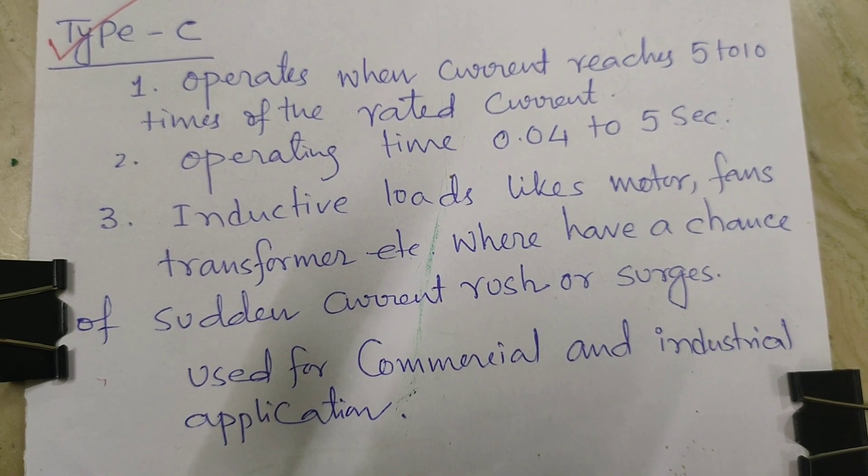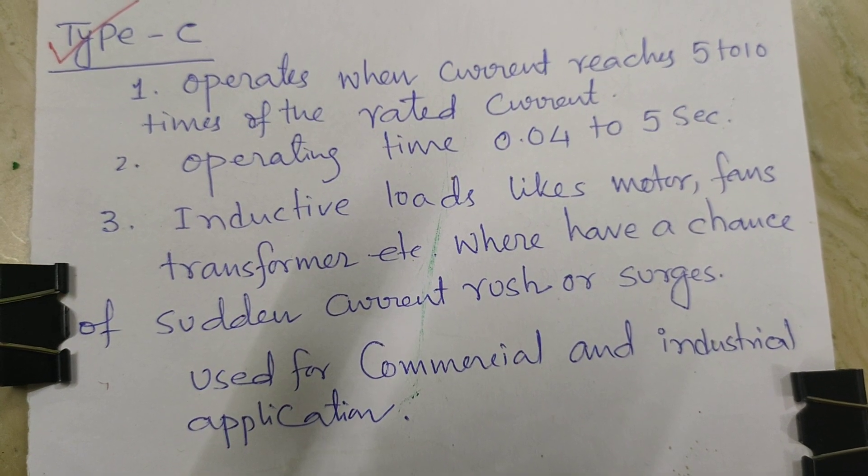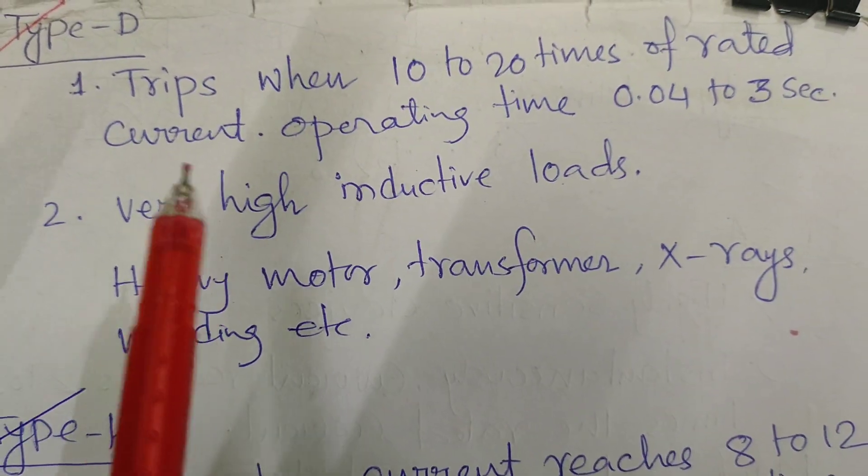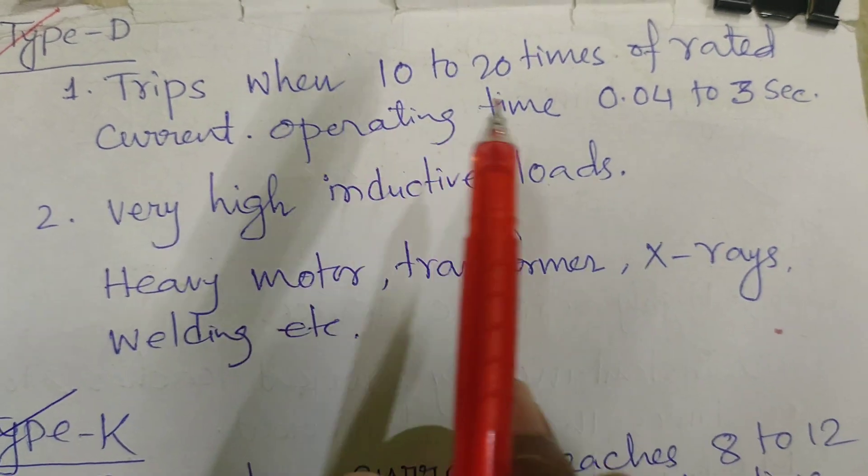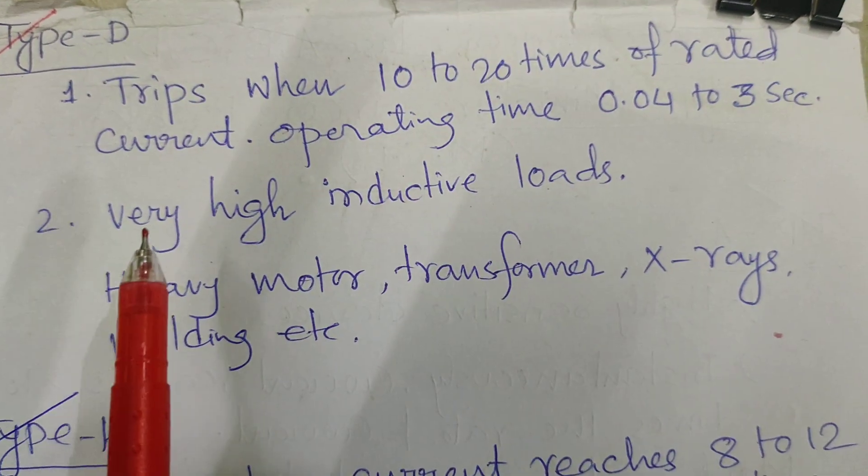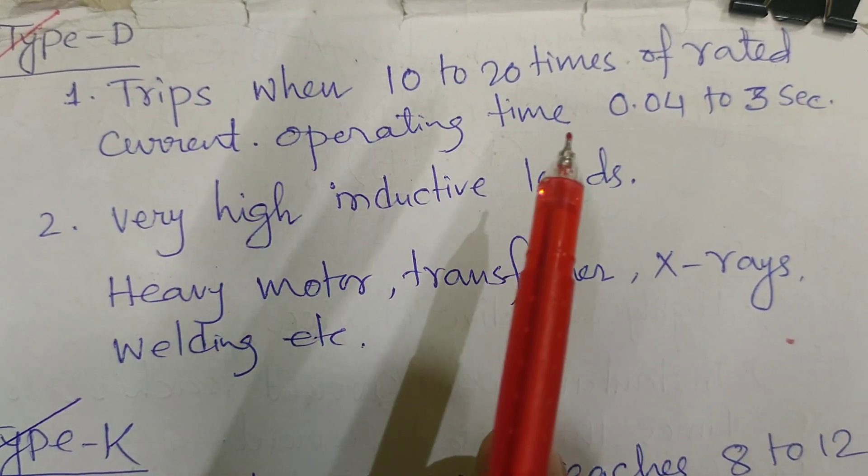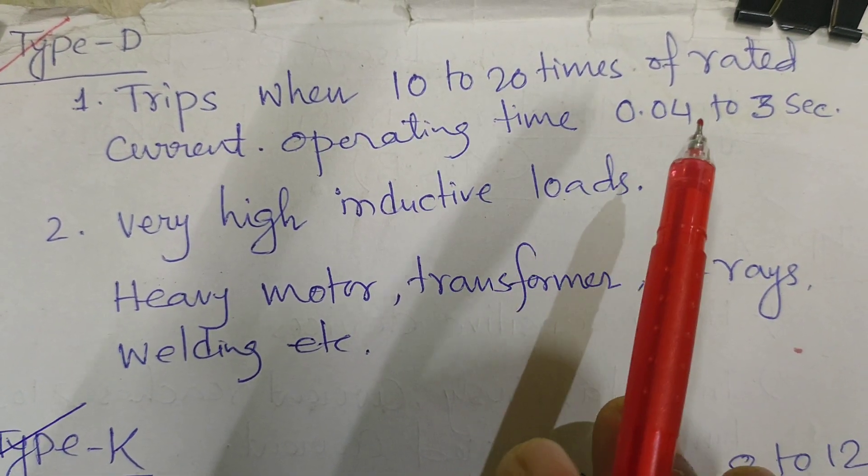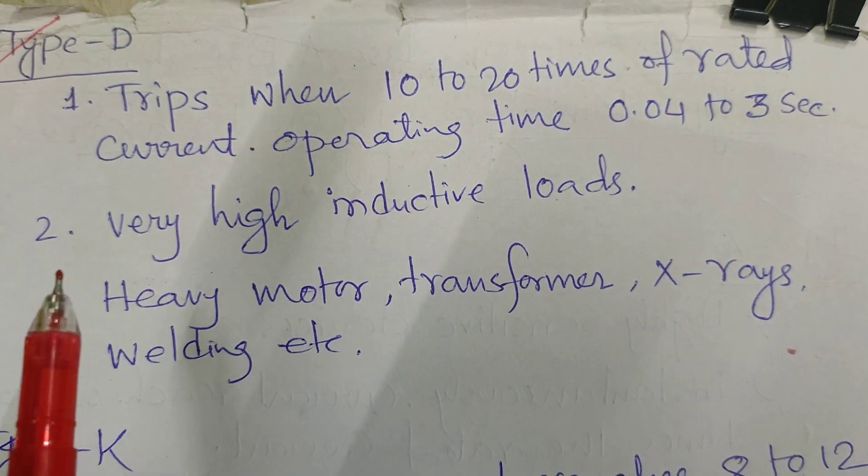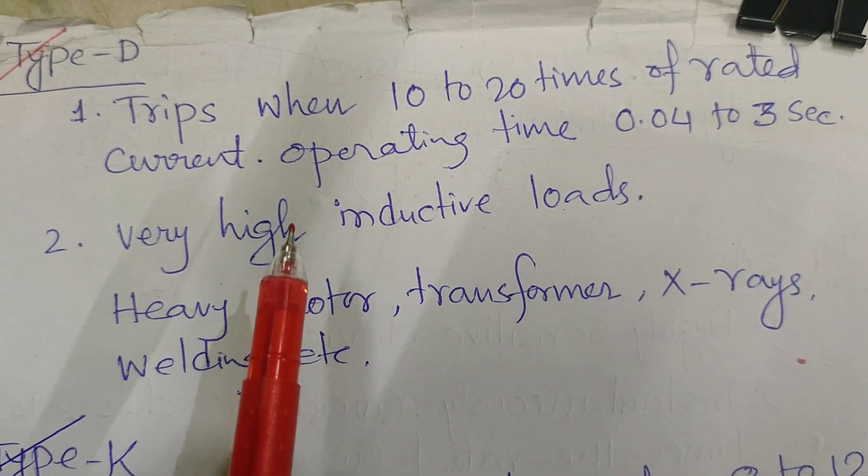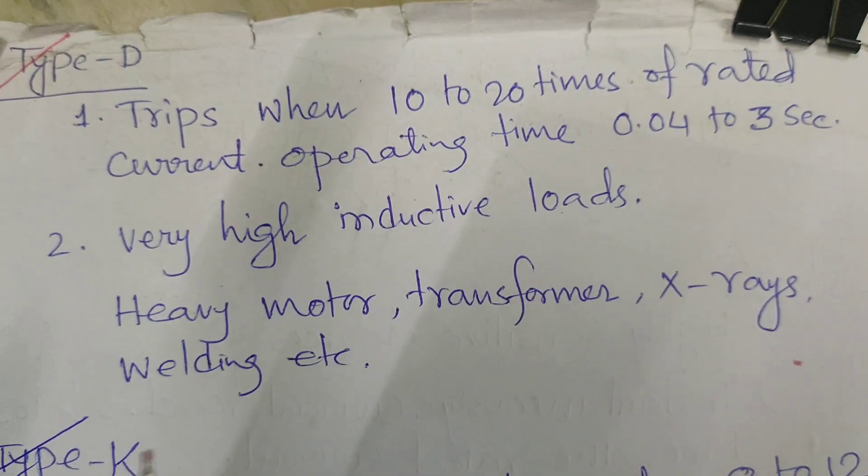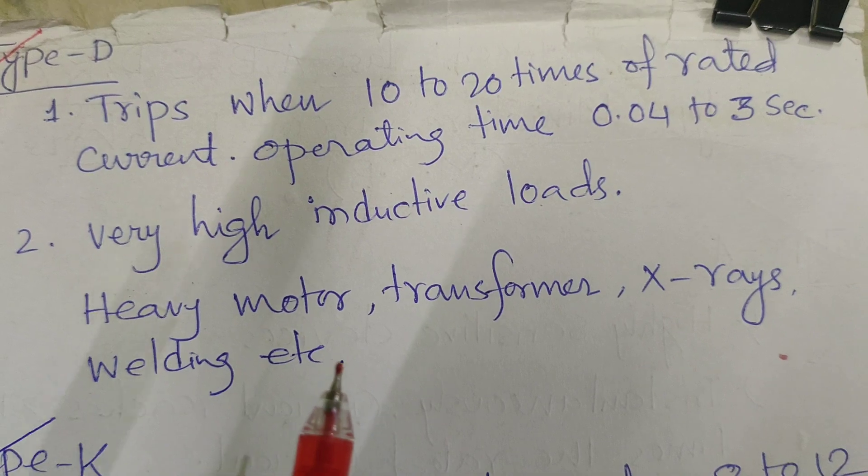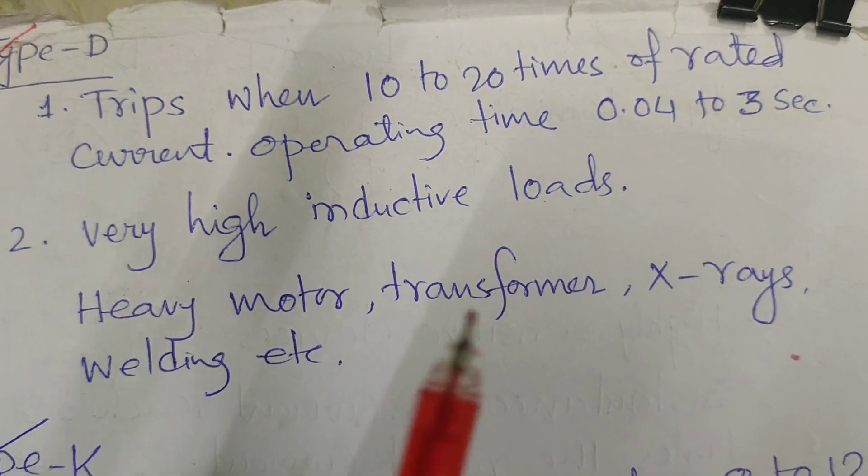D-type MCB has a function of trip when 10 to 20 times of rated current will flow. Operating time will be 0.04 to 3 seconds. It is being used for very high inductive loads, heavy motors, transformers, x-ray, welding, etc. We are using D-type MCBs.